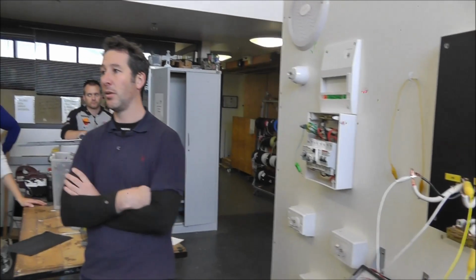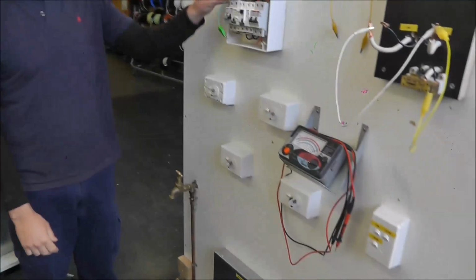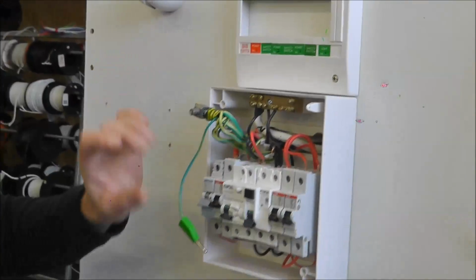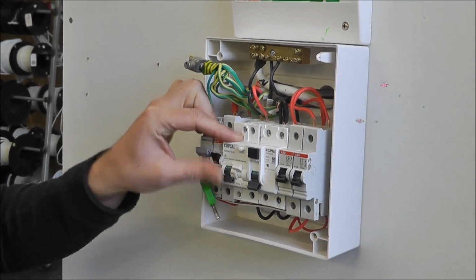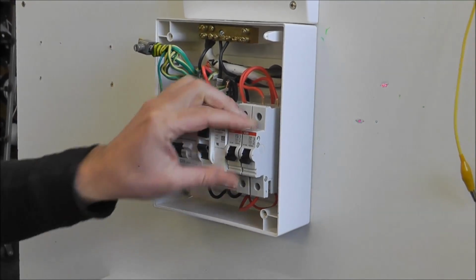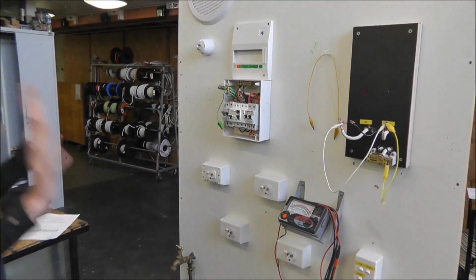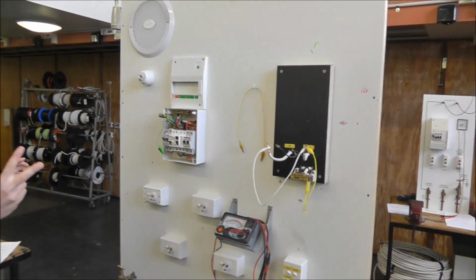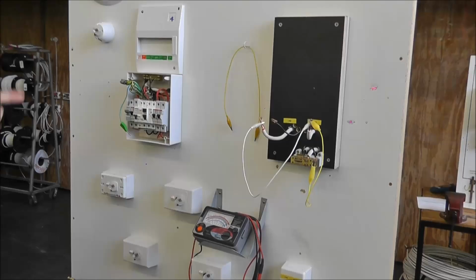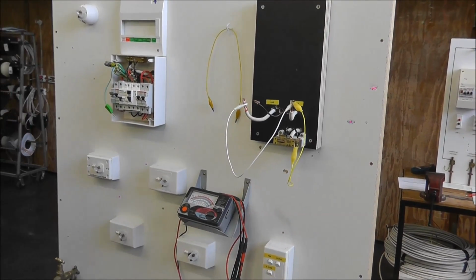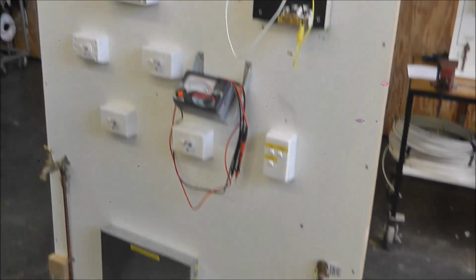Yep, okay. Now all my switches here are on. If I want to do a whole installation resistance test, should I have all my breakers on or off? Everything on, I've got to join it all up. All RCDs, all breakers on. Now let's just double check this. Think about this. Is everything joined up? Are live parts joined up? Yes. Are consumer's mains, actives joined up? Yes. Are all breakers and all circuits on? Yes. Are all switches on? Yes. Can I proceed?